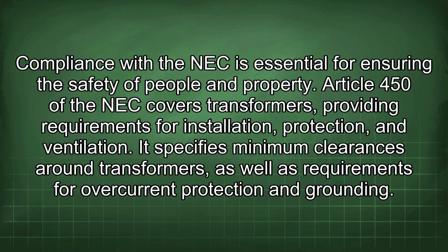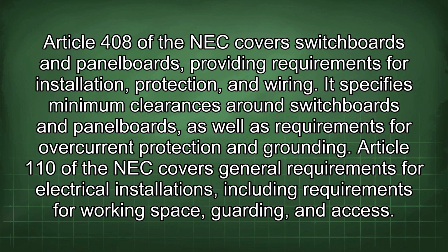Article 450 of the NEC covers transformers, providing requirements for installation, protection, and ventilation. It specifies minimum clearances around transformers, as well as requirements for overcurrent protection and grounding. Article 408 of the NEC covers switchboards and panel boards, providing requirements for installation, protection, and wiring. It specifies minimum clearances around switchboards and panel boards, as well as requirements for overcurrent protection and grounding.